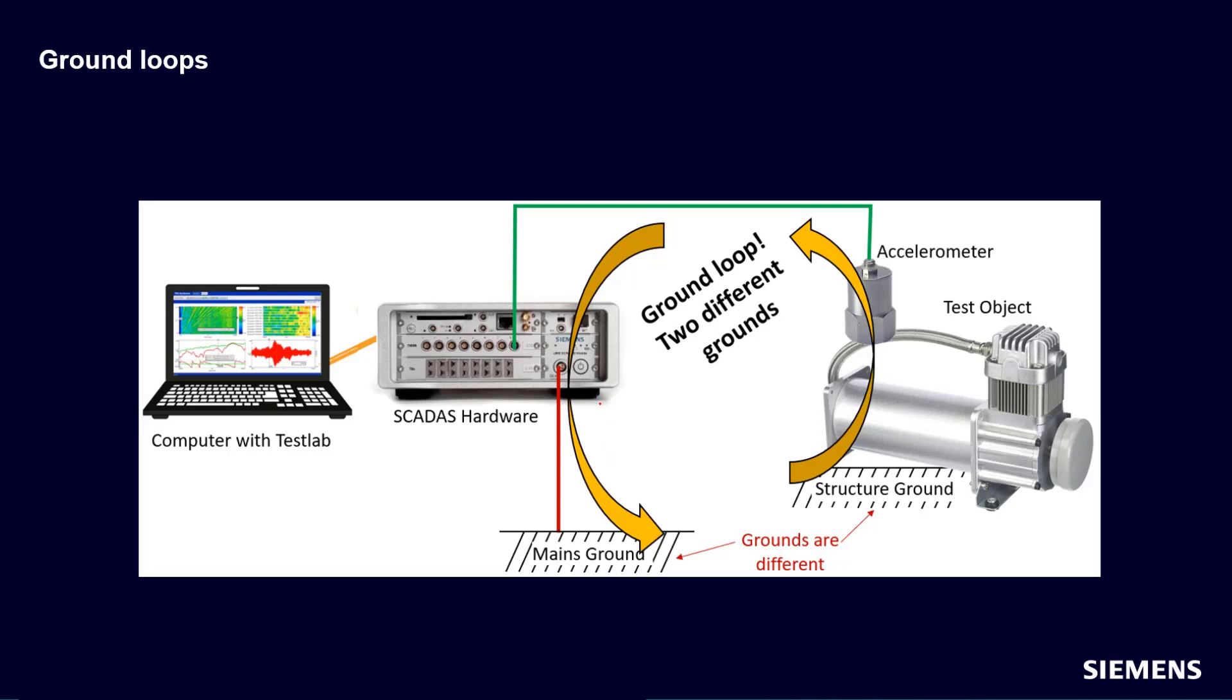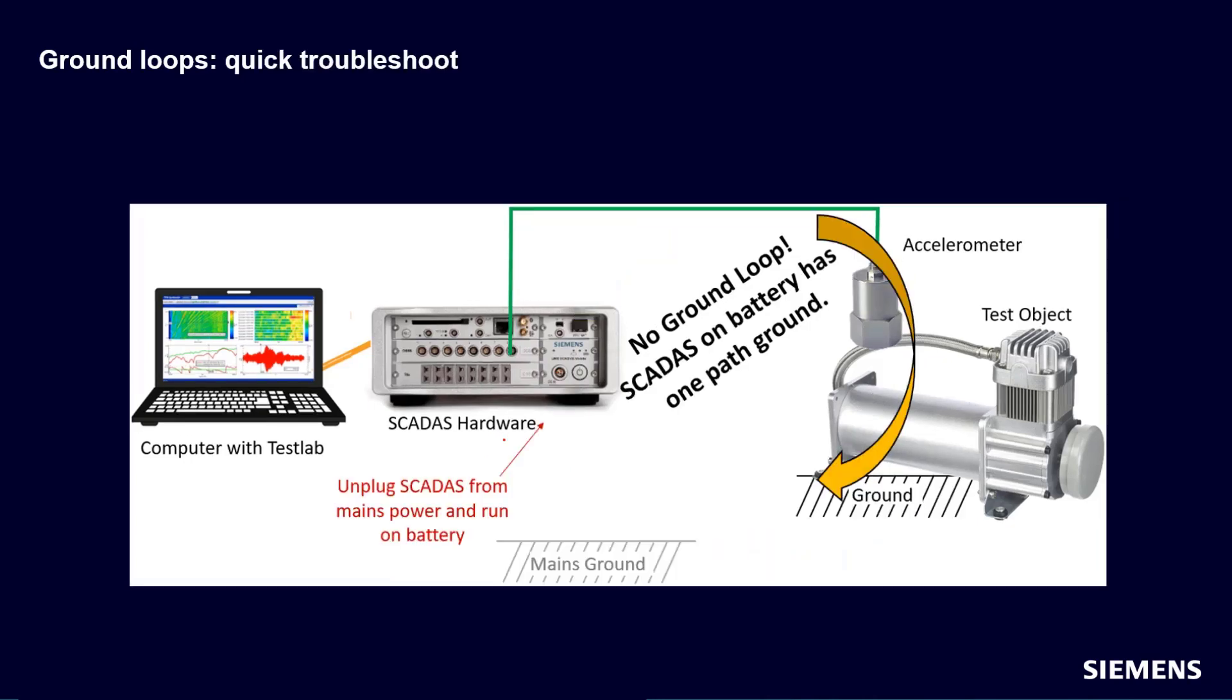If you're out in the field and you catch this, there's some things you could maybe do. You want to break one of these paths to ground. So for example, if you have one of our SimCenter SCADAS units, I can disconnect it from power because it has an internal battery that runs on DC. And when that is broken, there's only one path to ground. And if the electrical noise goes away, I know I have a ground loop. If it doesn't go away, then there's a chance that that 60 hertz is real. So quick troubleshooting, disconnect this.